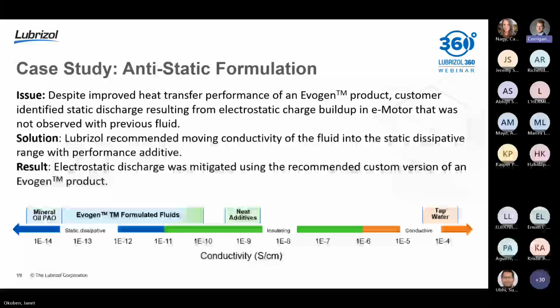So they put it back on us and asked if there was something we could do to resolve this issue. We developed an anti-static additive that we incorporate in a very small amount, which subtly boosts the electrical conductivity from the purely insulating regime toward the static dissipative regime. So similar to viscosity and flashpoint, we have the ability to formulate to really any conductivity on the spectrum using these additives.